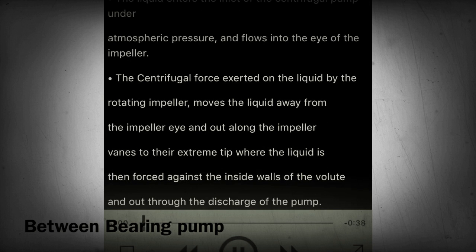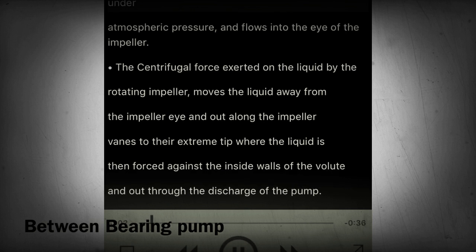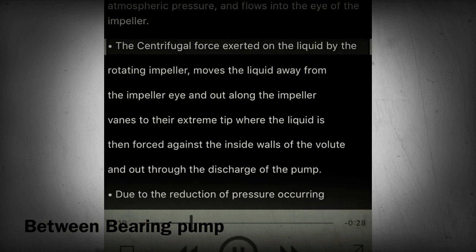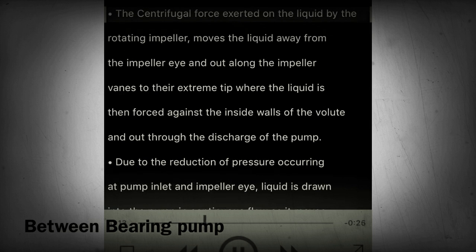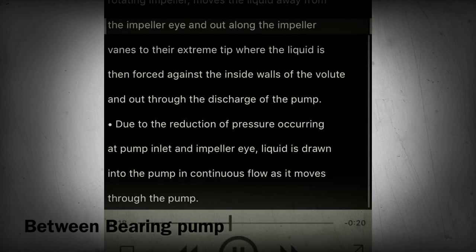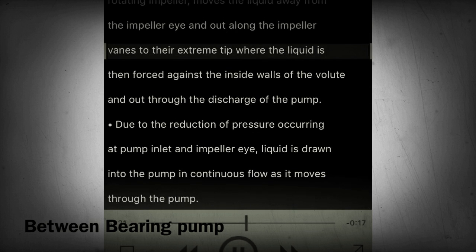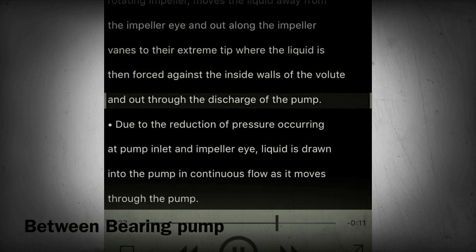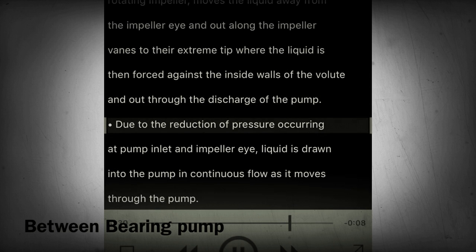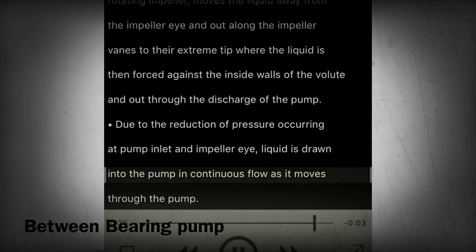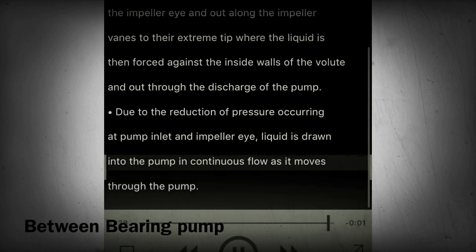Section 16 - Operating principles continued. The liquid enters the inlet of the centrifugal pump under atmospheric pressure and flows into the eye of the impeller. The centrifugal force exerted on the liquid by the rotating impeller moves the liquid away from the impeller eye and out along the impeller vanes to their extreme tip, where the liquid is forced against the inside walls of the volute and out through the discharge of the pump. Due to the reduction of pressure occurring at the pump inlet and impeller eye, liquid is drawn into the pump in continuous flow as it moves through the pump.